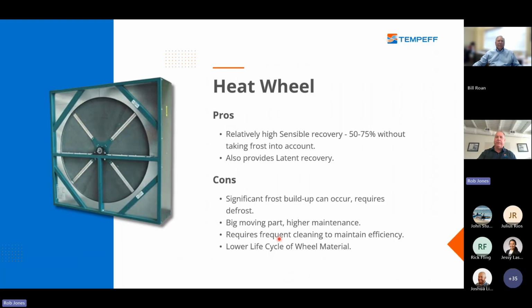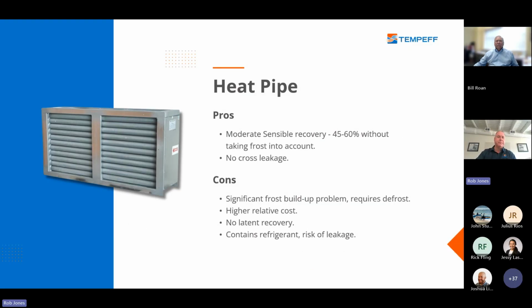This wheel requires a belt to drive it, and of course an additional actuator. Once again, due to the tight construction, especially around the flutes, it's easy for dirt and debris to build up on the wheels, causing them to be less efficient. Manufacturers will actually combat this by having a filter before and after the wheel. This drives up your pressure drop, size of your fans, and your energy consumption. More related to the energy wheels, they have a lower life cycle; some of them have to be replaced after 5 years due to the damage to the desiccant coating.